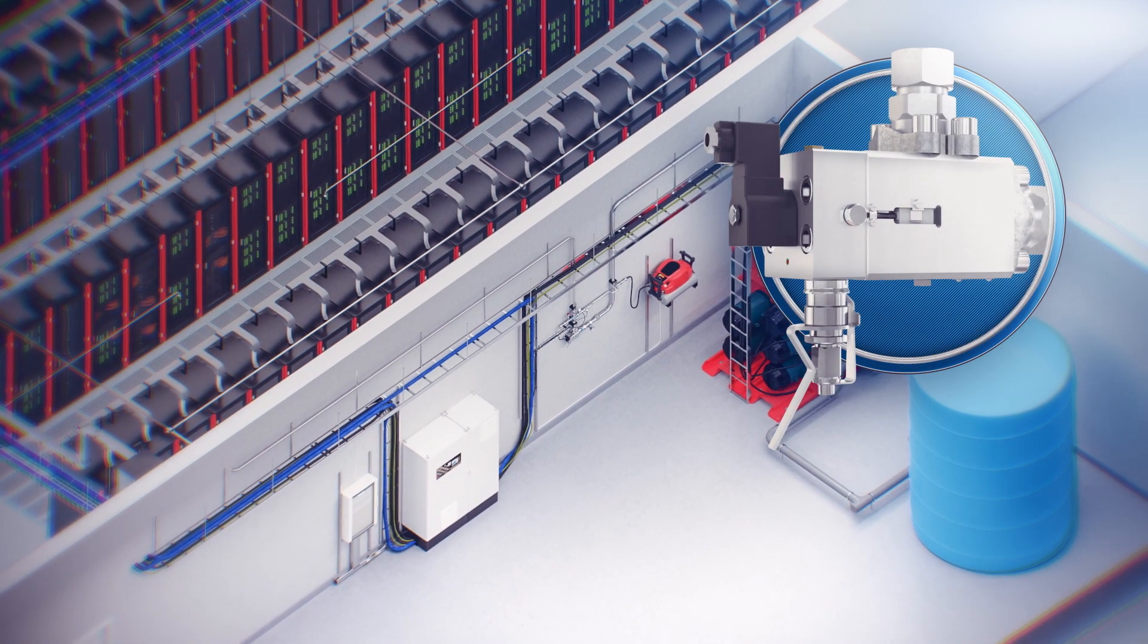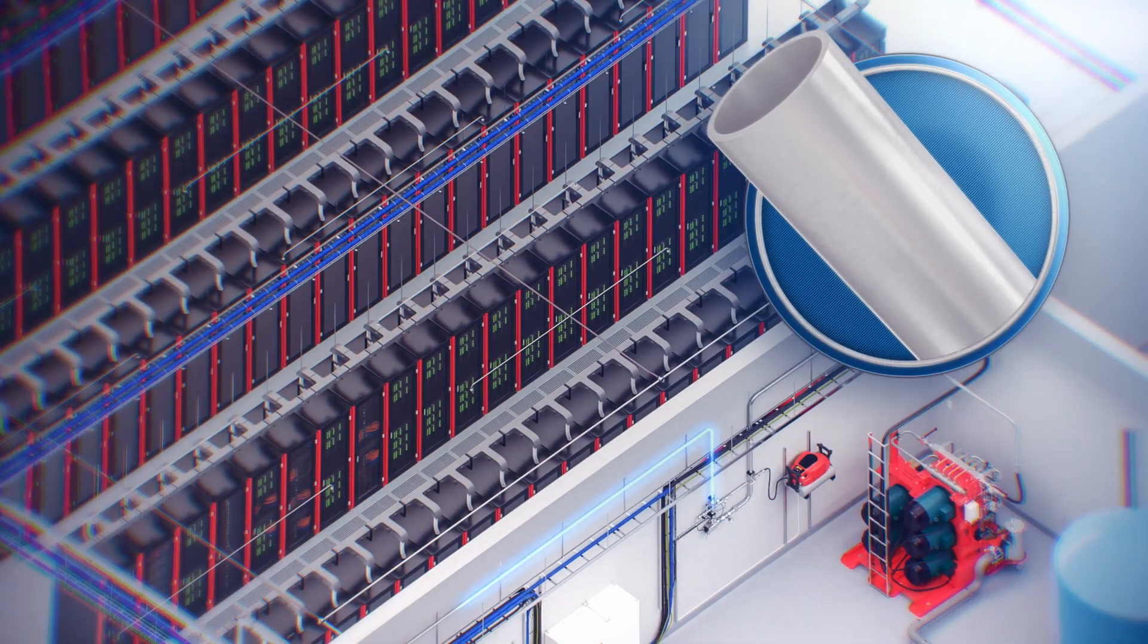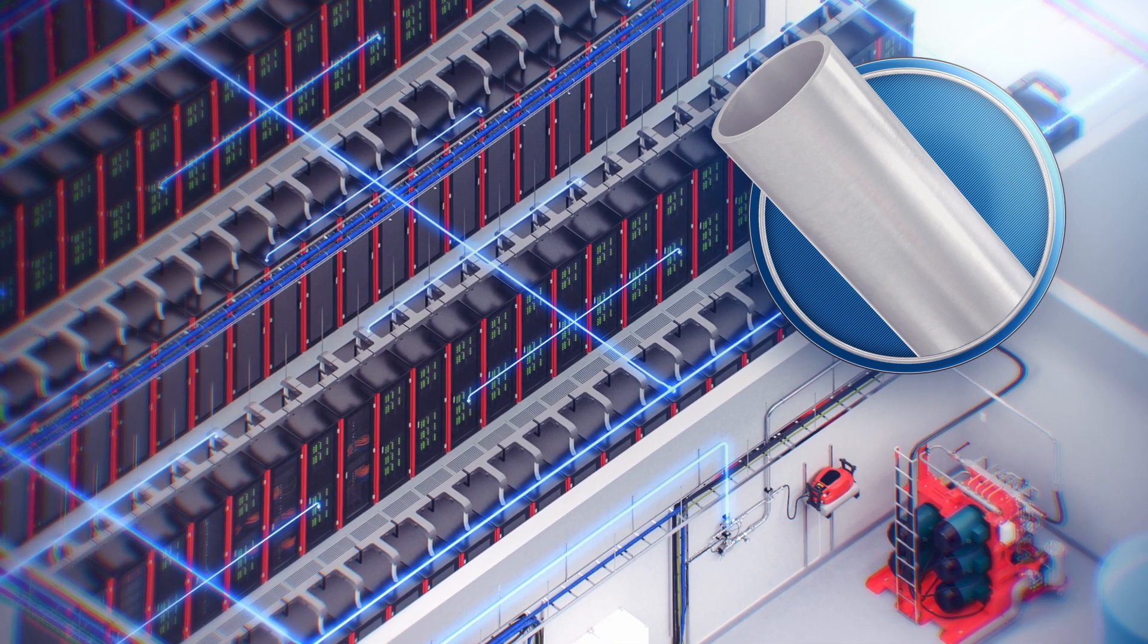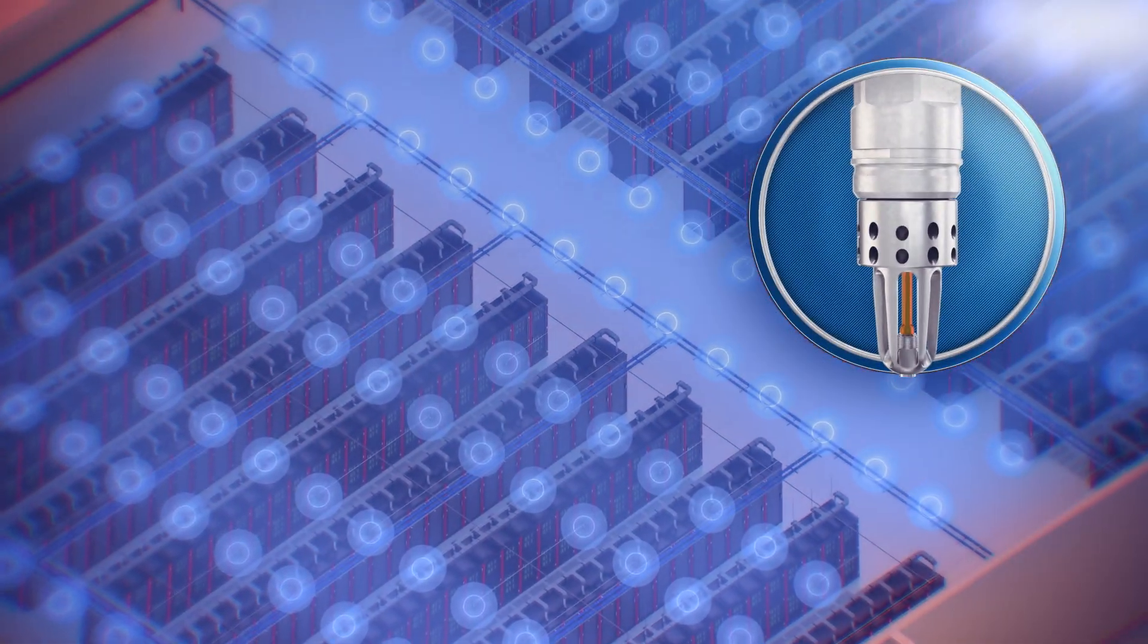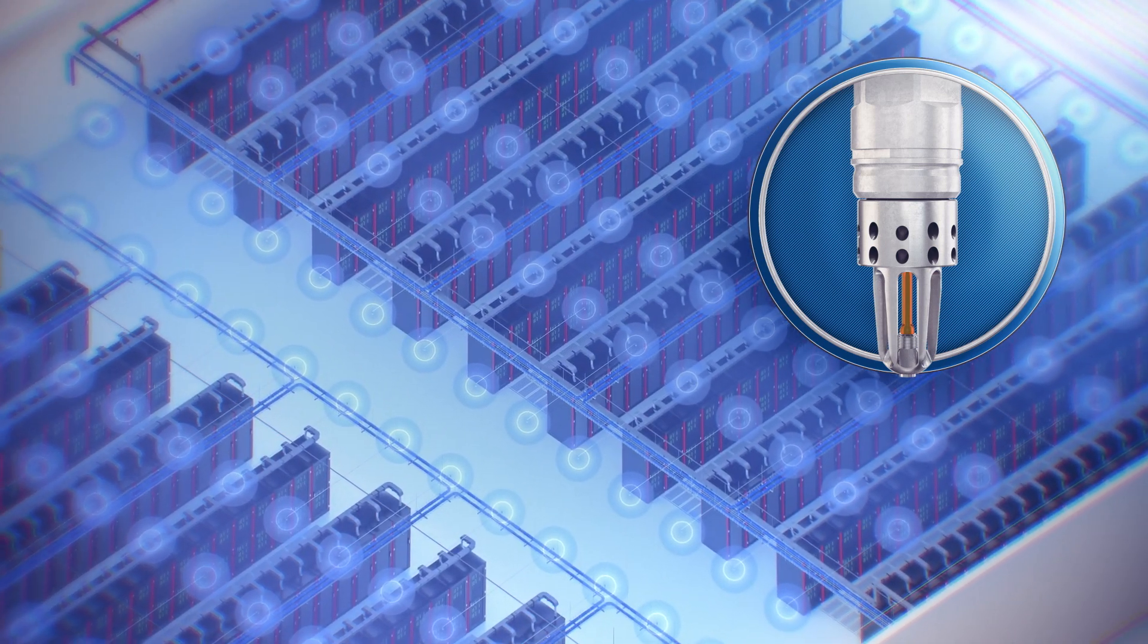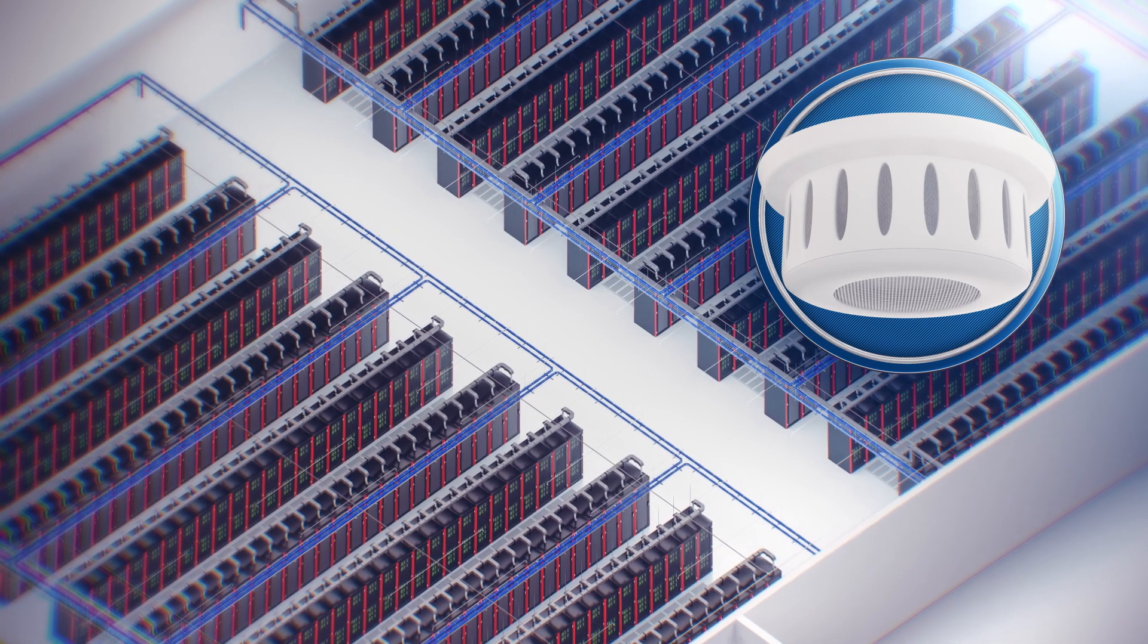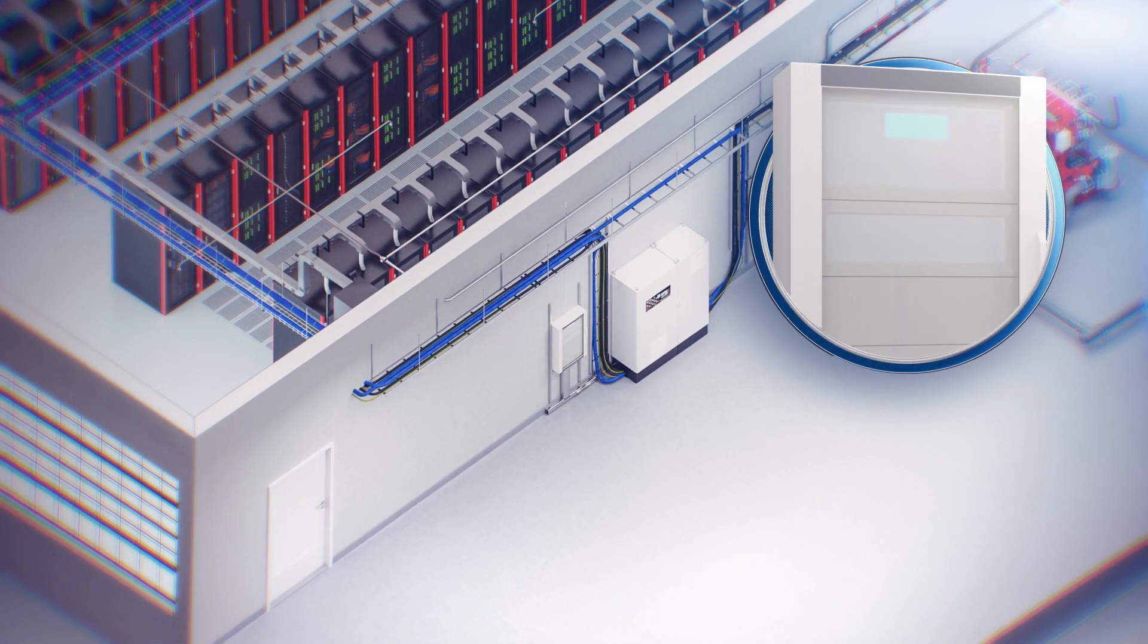Specifically designed valves are designed to prevent a false discharge. Pressurized water is distributed through stainless steel pipes. And finally, the layout of the sprinklers is designed to fit the criteria determined by full-scale fire tests and approvals. Other components that the system requires are detectors and a release panel that functions as the brain for the whole system.